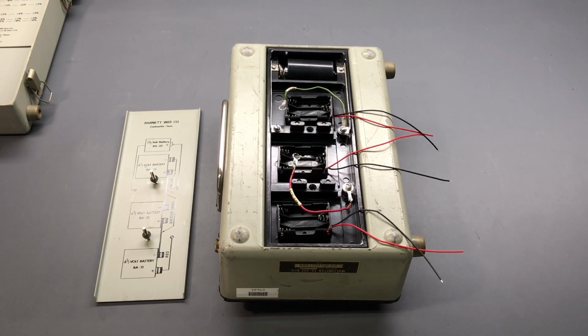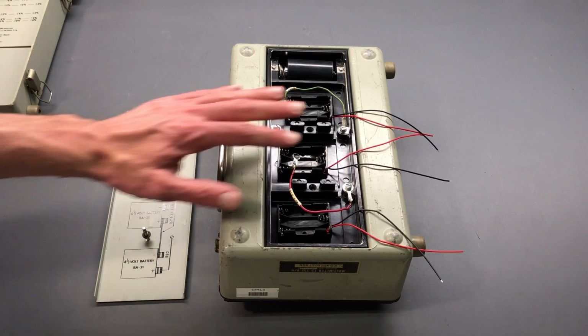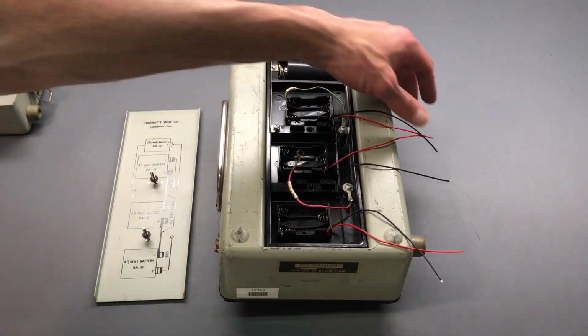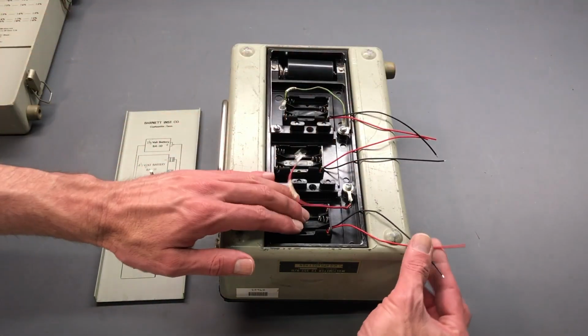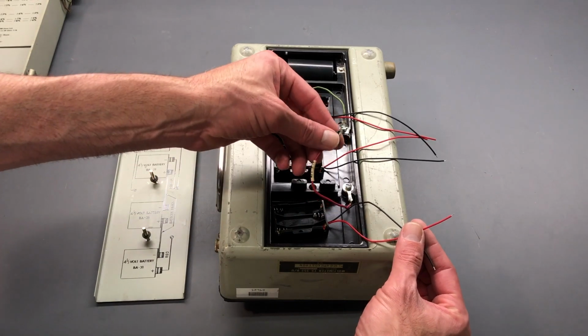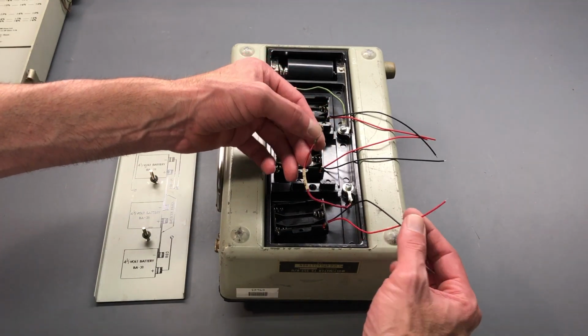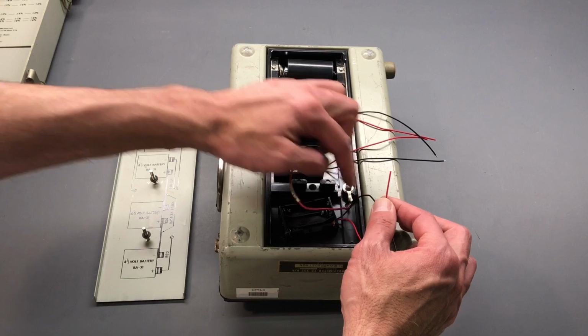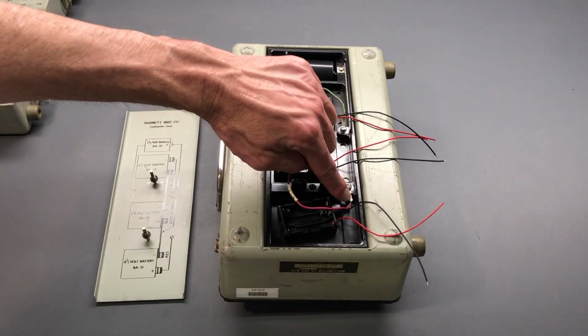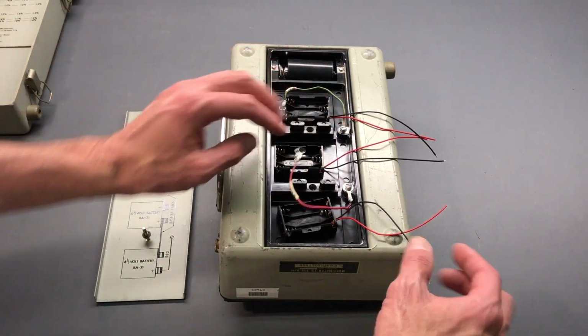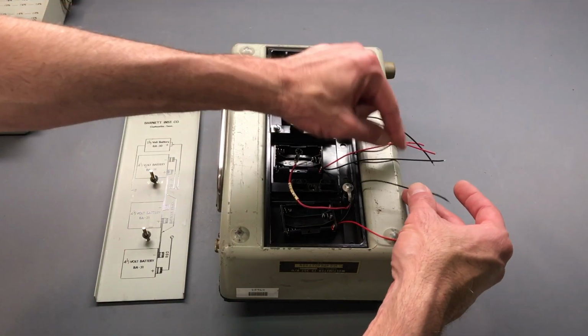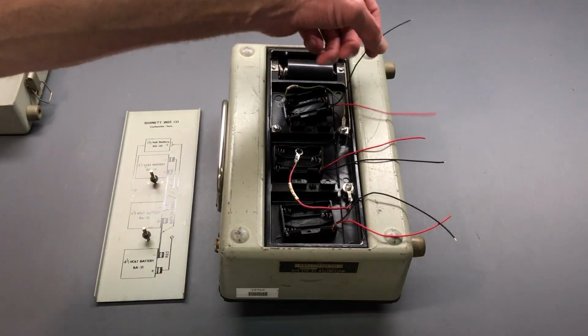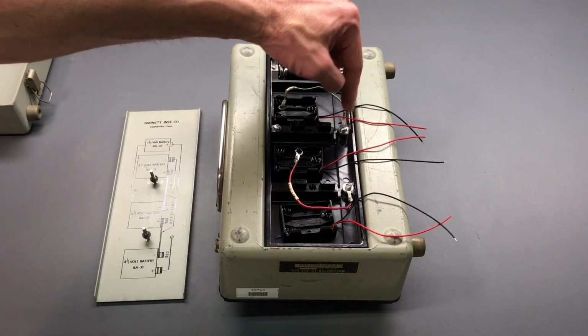So the next thing I need to do is make the wiring connections here, solder these, use some heat shrink, and join them all in series. This red lead is the positive input from the batteries, so it will join here. I'll get rid of the original wire and make the connection right on this terminal. The black lead goes to the red, black over to red, and the final black lead goes where this green wire attaches.